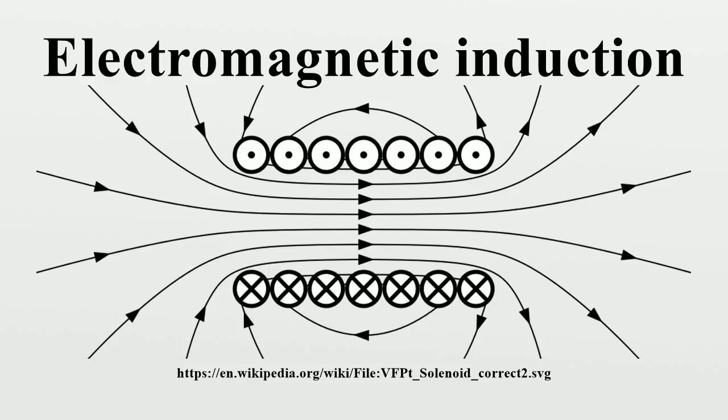Eddy currents. Conductors moving through a uniform magnetic field, or stationary within a changing magnetic field, will have currents induced within them. These induced eddy currents can be undesirable, since they dissipate energy in the resistance of the conductor. There are a number of methods employed to control these undesirable inductive effects. Electromagnets in electric motors, generators, and transformers do not use solid metal, but instead use thin sheets of metal plate, called laminations. These thin plates reduce the parasitic eddy currents, as described below.